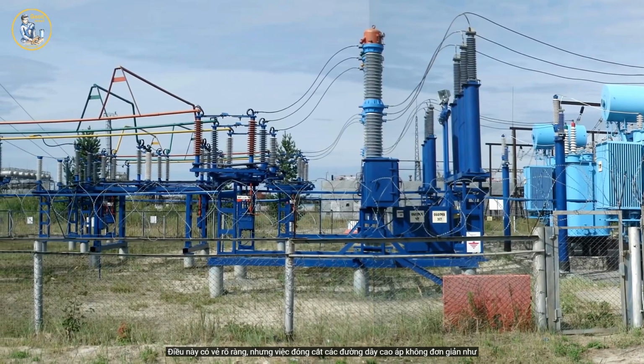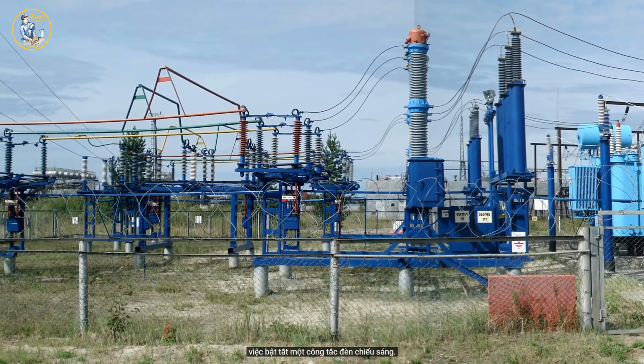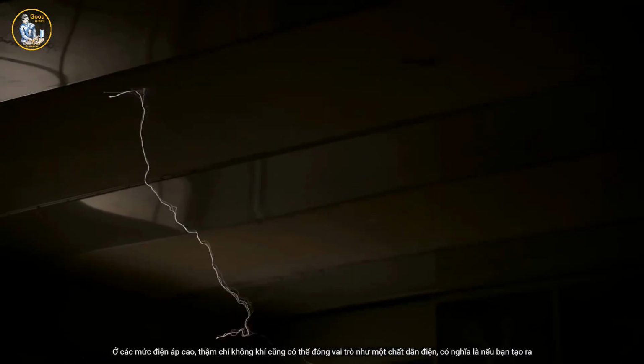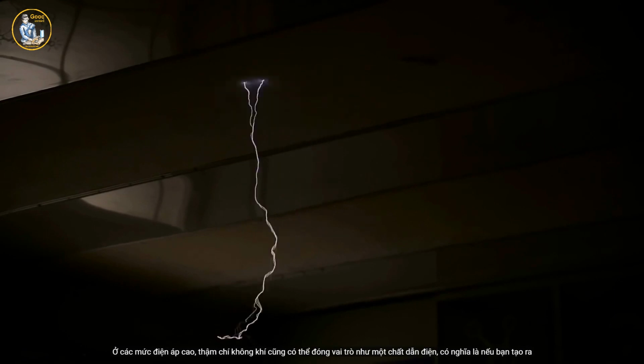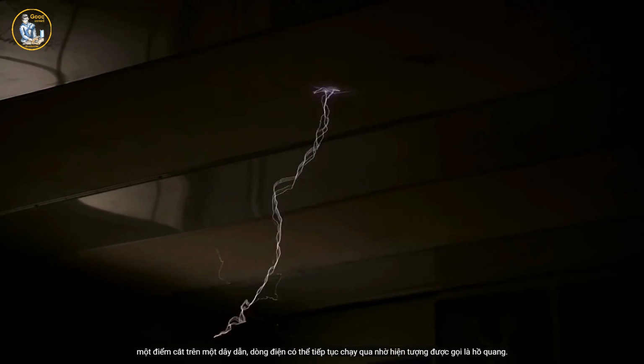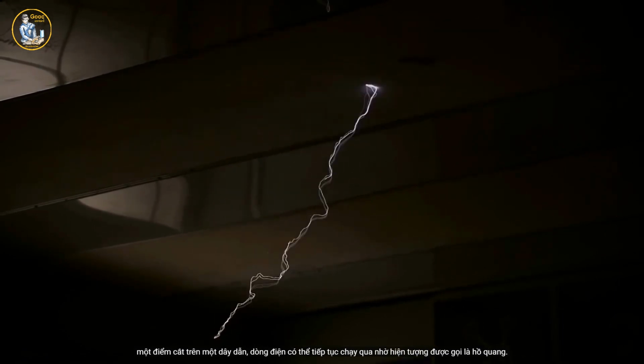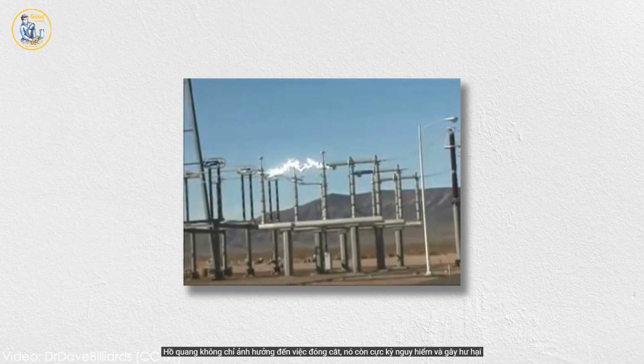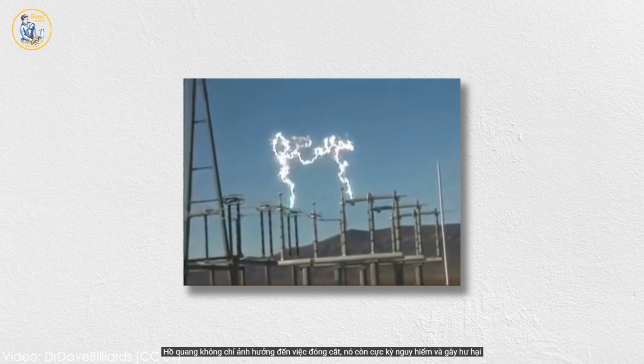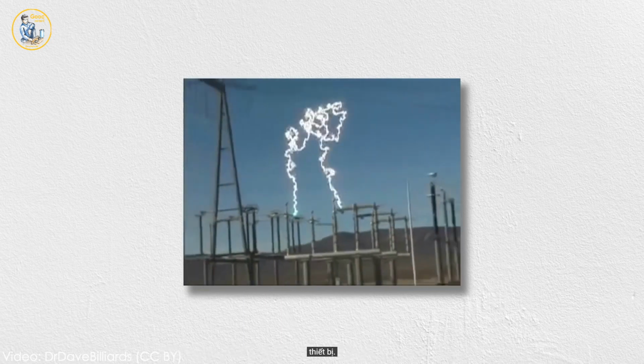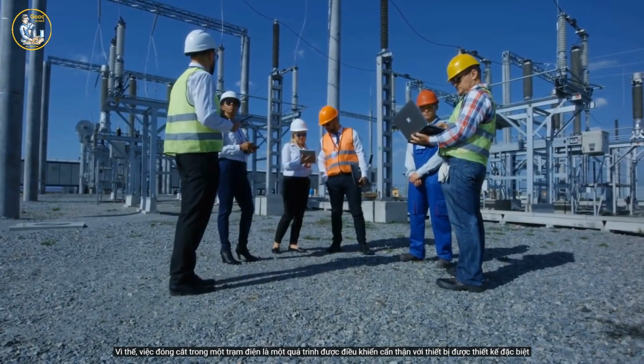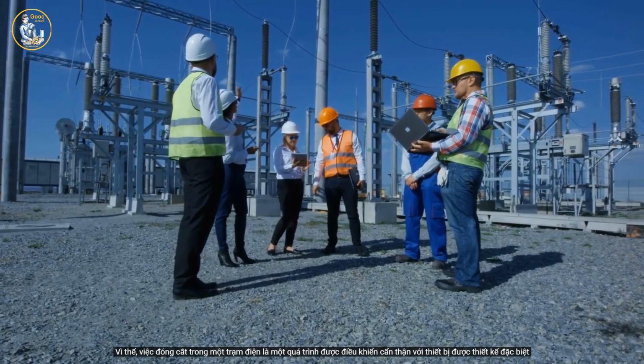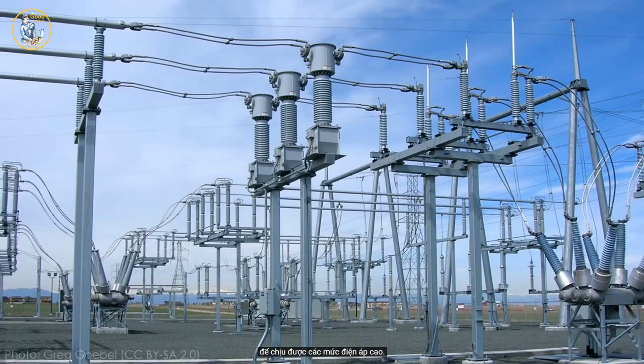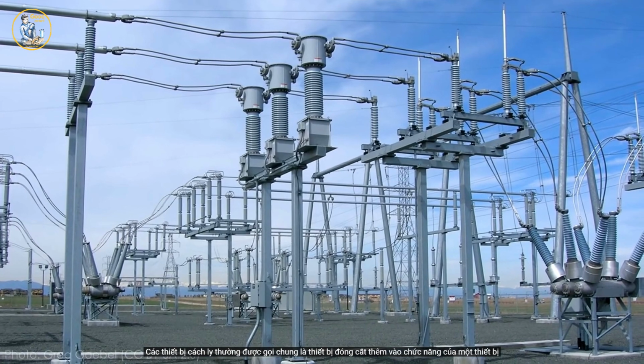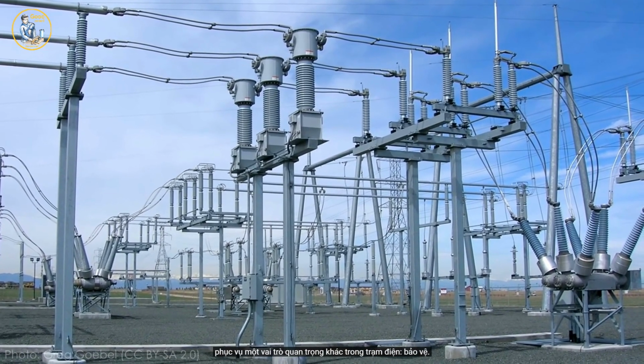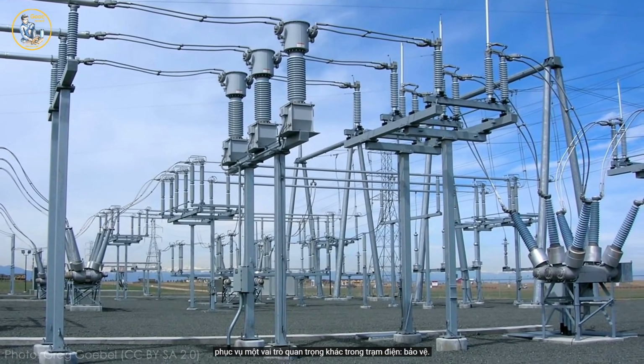This may seem obvious, but turning on and off high voltage lines isn't as simple as flipping a light switch. At high voltages, even air can act like a conductor, which means even if you create a break in the line, electricity can continue flowing in a phenomenon known as an arc. Not only does arcing defeat the purpose of the switch, it is incredibly dangerous and damaging to equipment. So switching in a substation is a carefully controlled procedure with specially designed equipment to handle high voltages.